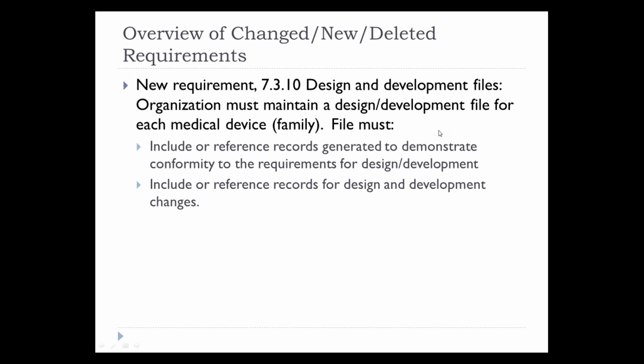Okay, new requirement 7.3.10, design and development files. If the organization is design responsible, they have to maintain a design and development file for each medical device or family. The file must include or reference records generated to demonstrate conformity to the requirements for design and development. So your design review records, your planning, your verification and validation, and any necessary actions resulting from those activities. And they need to include or reference records for design and development changes.